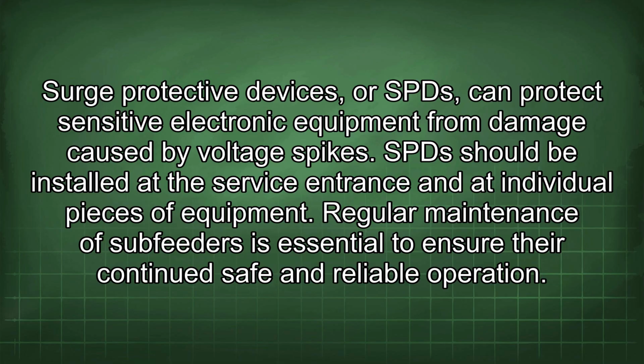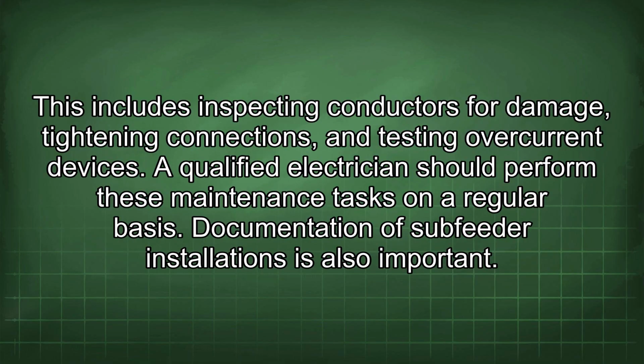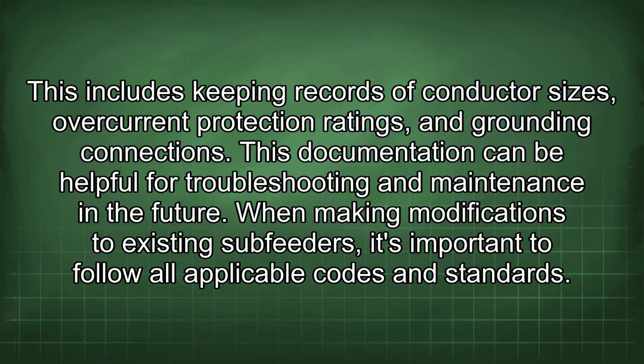Regular maintenance of subfeeders is essential to ensure their continued safe and reliable operation. This includes inspecting conductors for damage, tightening connections, and testing overcurrent devices. A qualified electrician should perform these maintenance tasks on a regular basis. Documentation of subfeeder installations is also important. This includes keeping records of conductor sizes, overcurrent protection ratings, and grounding connections. This documentation can be helpful for troubleshooting and maintenance in the future.